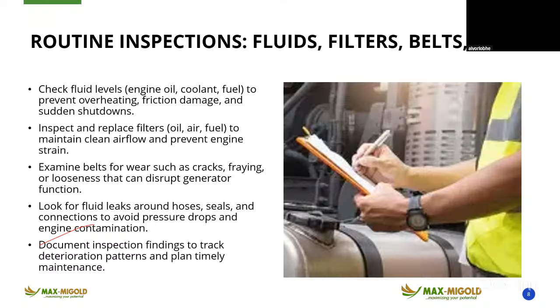If someone asks, is it good to top up oil? No. If you start noticing a shortage of oil in your generator, that means there's a problem. Don't start topping it up. Record it down: I noticed that the oil has dropped. We have watched for the past one week, the oil is still dropping. You call for attention, reach out for an expert, a professional who will come and do a thorough inspection based on your observation and rectify the problem. If you keep topping up the oil, you are not solving the problem. You are only prolonging the issue, and one day the topping may not work. It will lead to total breakdown of the generator.